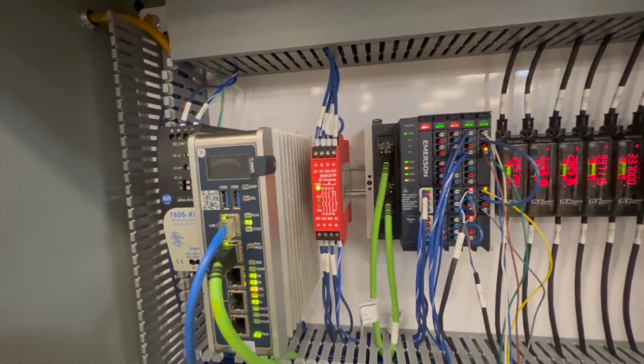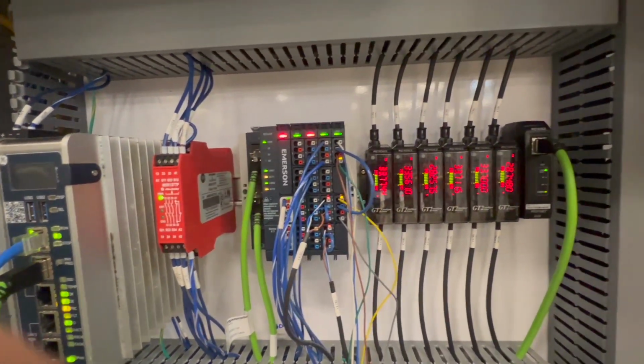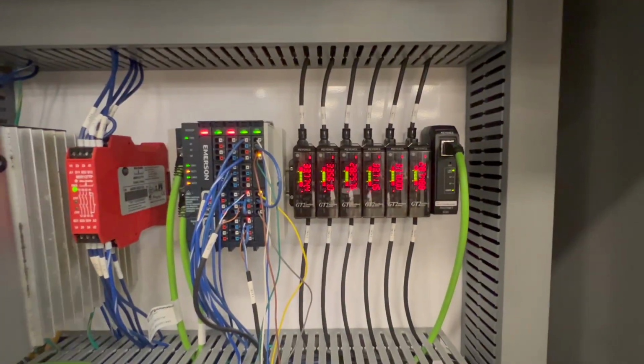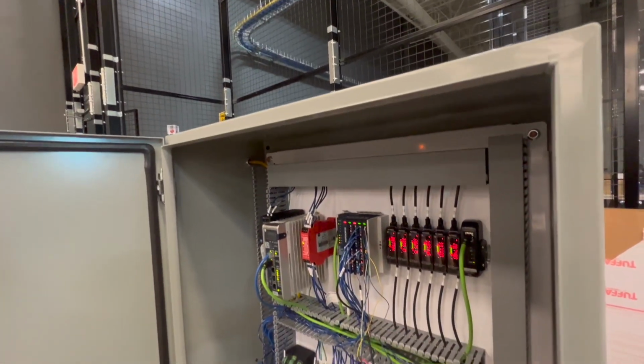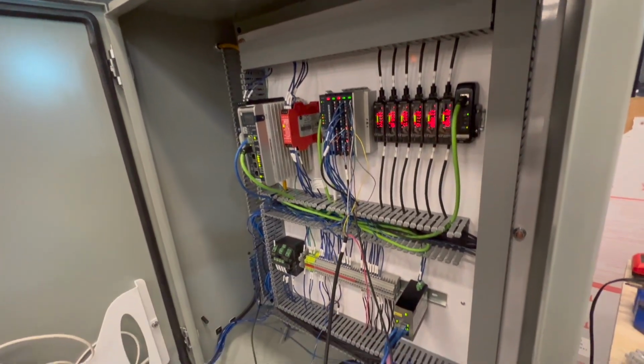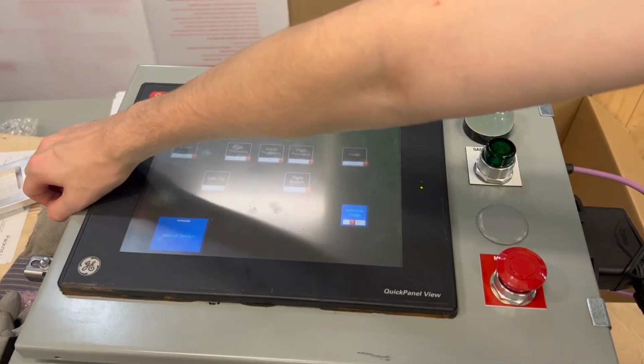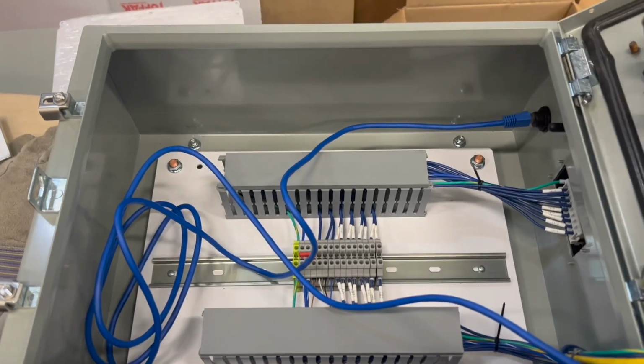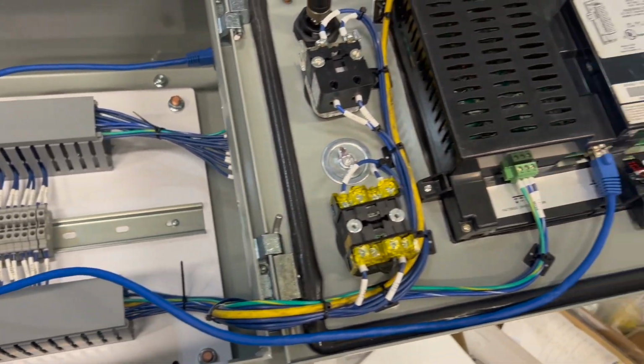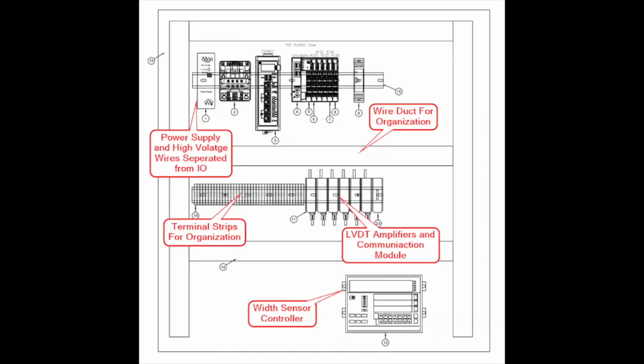The electronics that control the device are contained within two enclosures. The main enclosure houses most of the electrical components, and the HMI enclosure houses the HMI and other human interface devices, such as an e-stop, safety reset button, and stack light. The main enclosure is powered by a standard 120 volt outlet, which feeds a 24 volt 5 amp power supply. The power supply is located in the top left corner of the cabinet to isolate the incoming 120 volt cable from the electrically sensitive sensor wires.